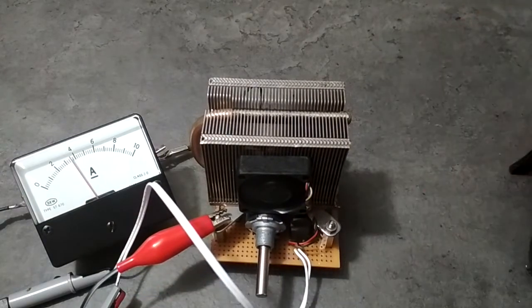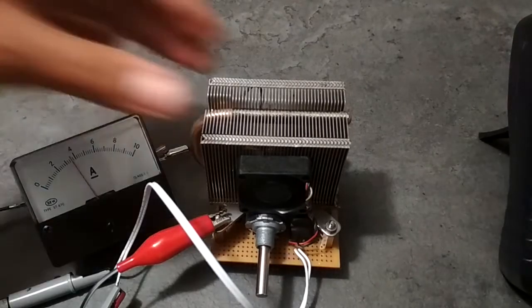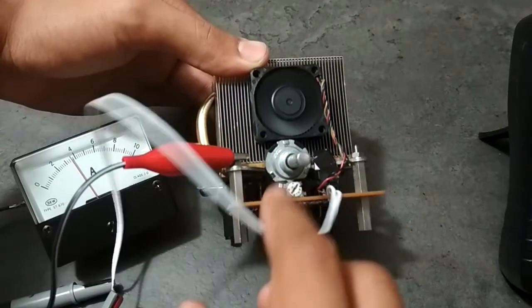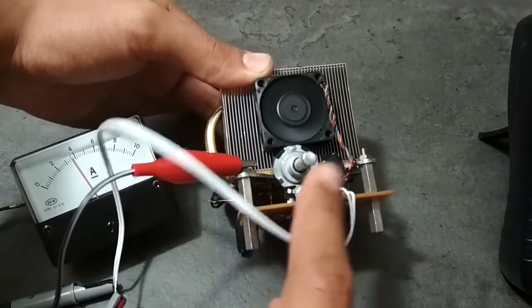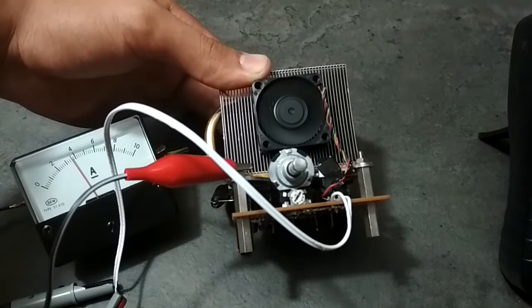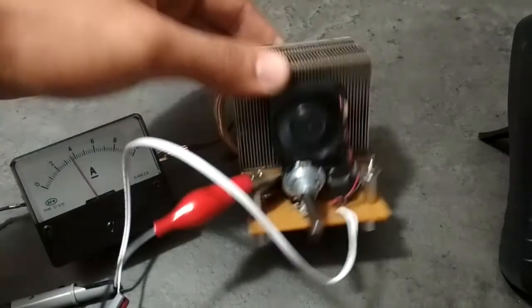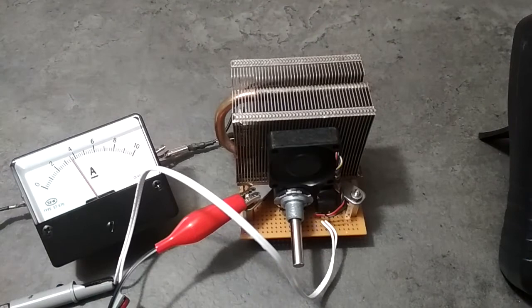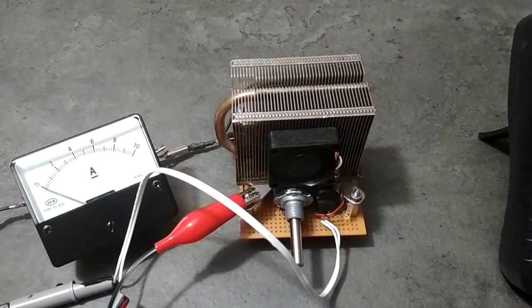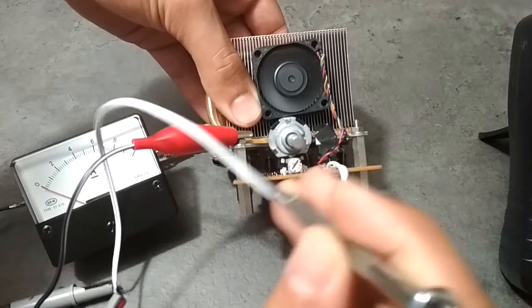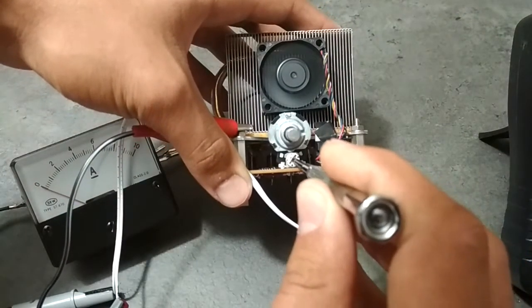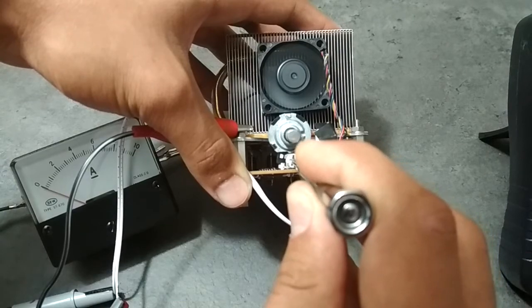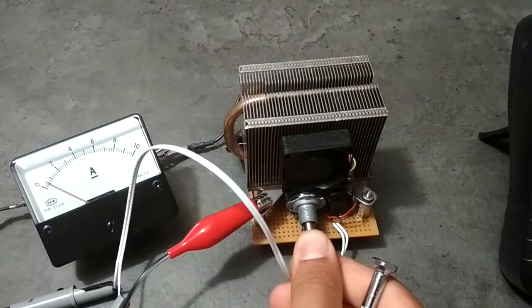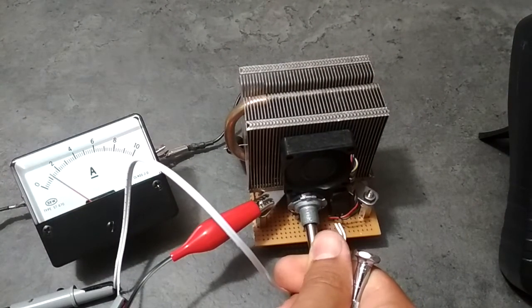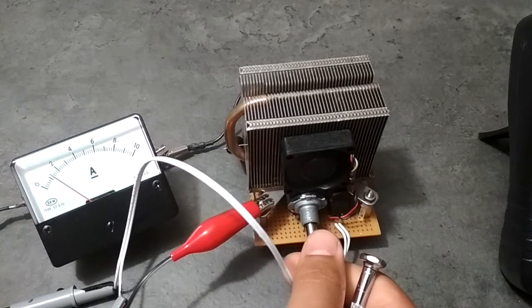There's a second potentiometer underneath. Basically, by turning this, we can adjust the sensitivity of the main potentiometer. Now, if I can find a screwdriver. So as you can see now, I'll put it at 0. And if I turn the potentiometer under here to the left, it will make the main one less sensitive. As you can see, I turn it all the way to the right, and it's a little over 1 amp.